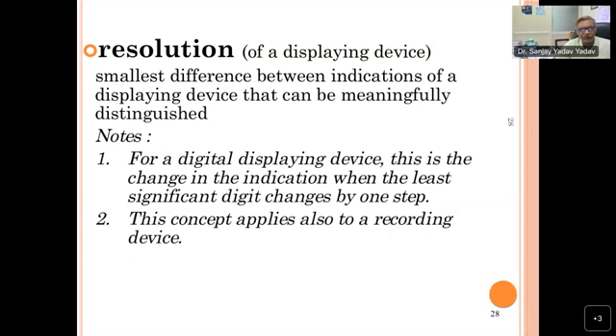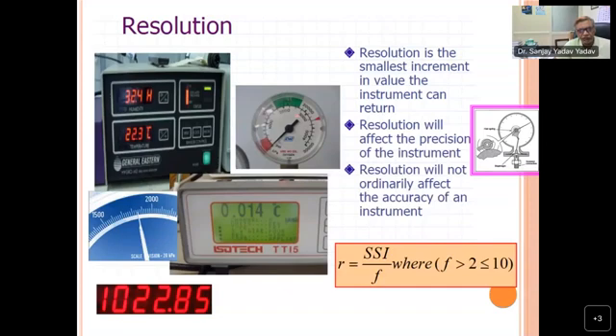Then comes the very important term, resolution. So it's the smallest difference between indications of a display device. This is another important characteristic of a measuring instrument. Now you see this particular slide, you will find the different resolutions of the gauge in digital format and also in analog type. So the smallest measurement you can make using this instrument is the resolution, but how can you take this quantity in terms of the uncertainty?